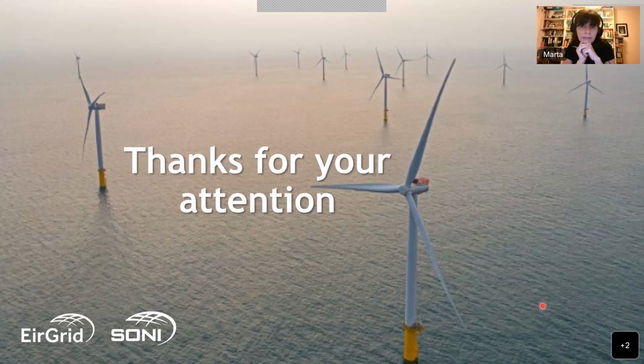Do you check the fault ride-through capability of IBRs in the online assessment? So the customers, before they connect, as part of the connection process, have to do a number of assessments and studies, and demonstrate to us that the plant is capable of riding through faults according to the grid code requirements. They need to provide a report with that assessment, and provide the models that match that assessment. So that is part of the pre-connection assessment process.